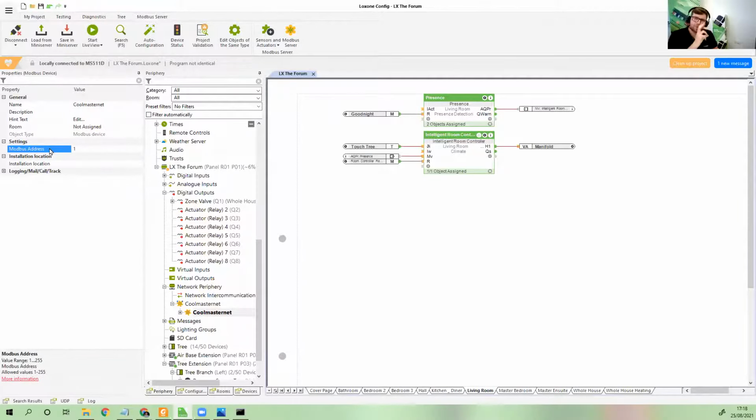That's because you may have one main server with several devices on it. And remember, Modbus is an addressable system. If it's just a single device, single address, it's probably address 1, which in this case it is. Brilliant. We then need to start adding in registers. Now, registers are the way that Modbus works. It speaks on registers.